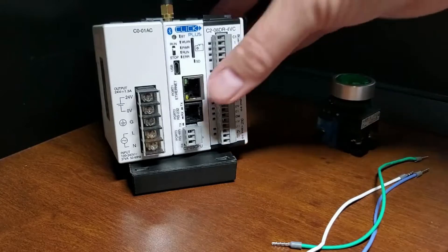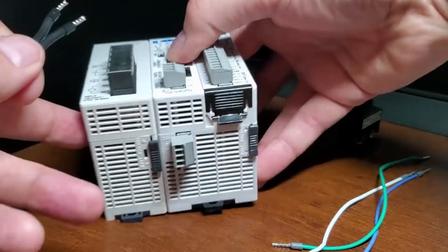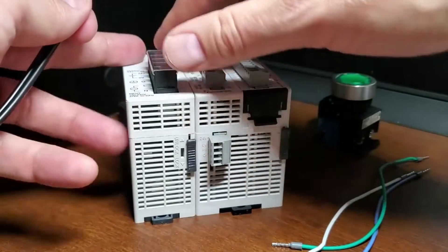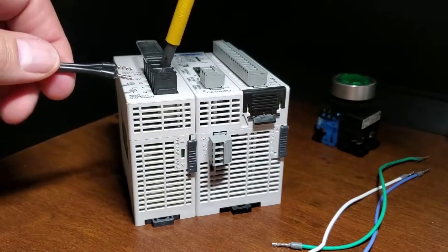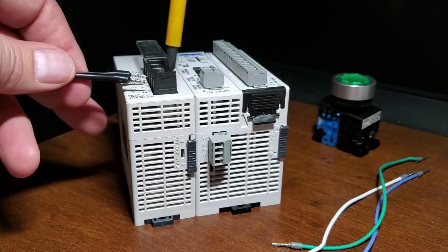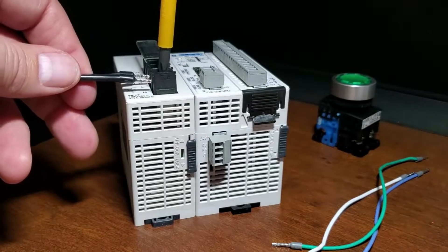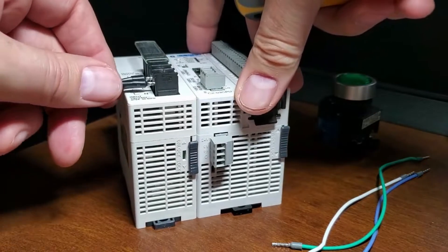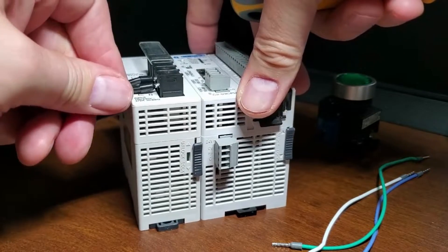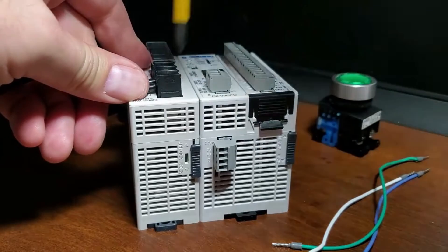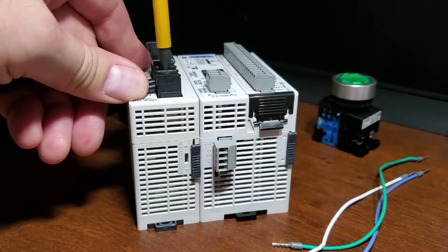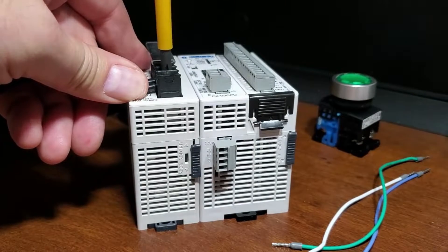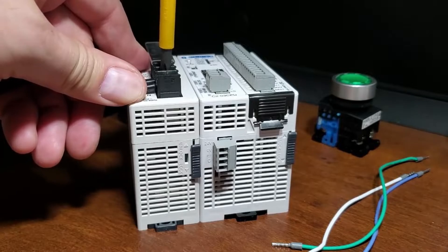24-volt DC power is supplied to the Click Plus CPU through a wiring connection from the power supply output to the 4-pin connector on the bottom of the CPU unit. 16-28 gauge wiring is supported. Crimping ferrules on all wire terminations are recommended for a more secure connection.